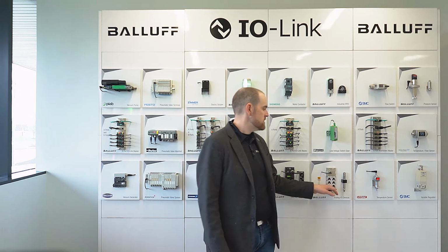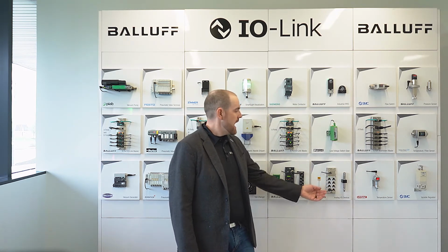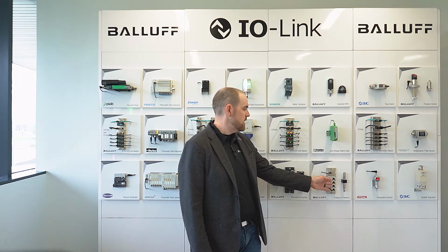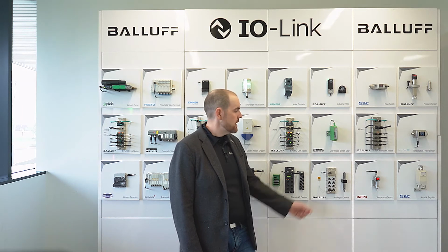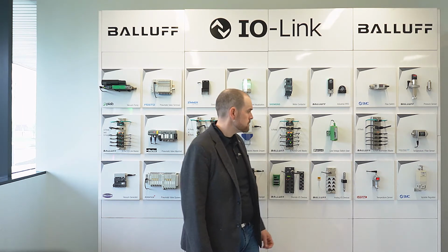You get to pick and choose what you want for each of these ports, and that has a high value if you have a lot of analog signals on your machine. What's cool is the analog to digital conversion is done here and then sent over the IOLink communication, so you don't have to worry about any noise or shielding issues inside a controls cabinet.